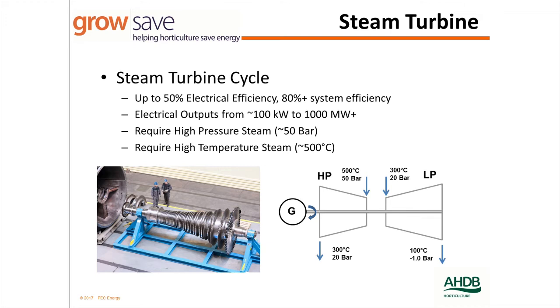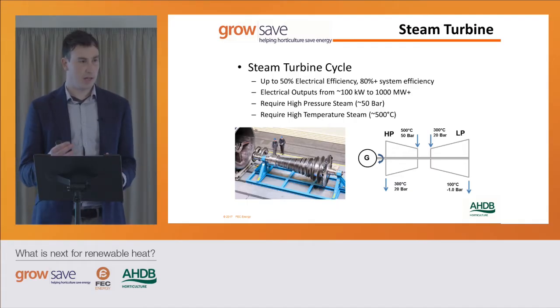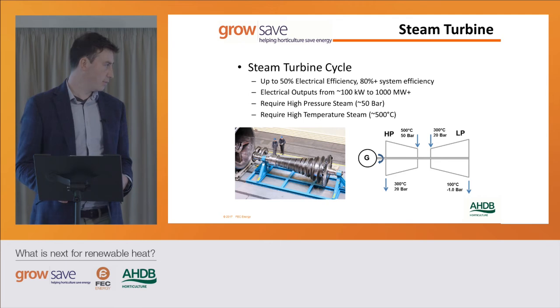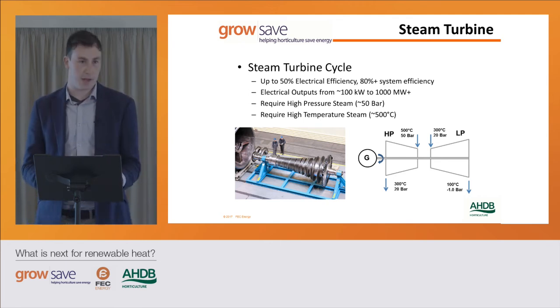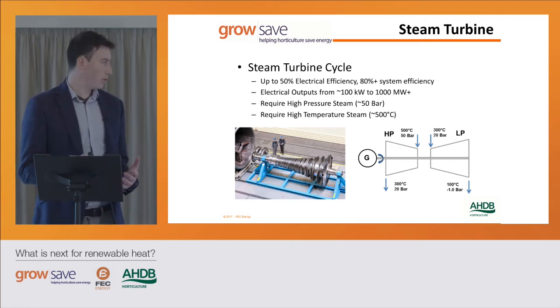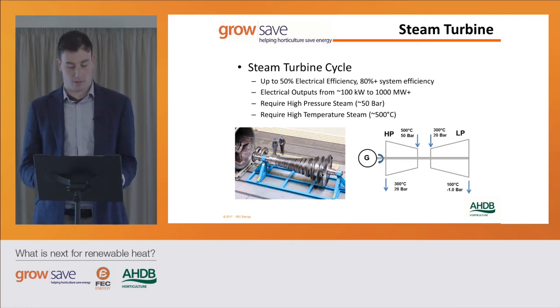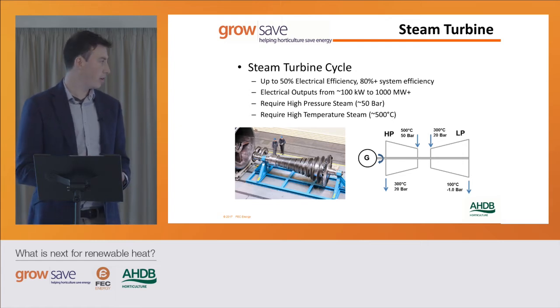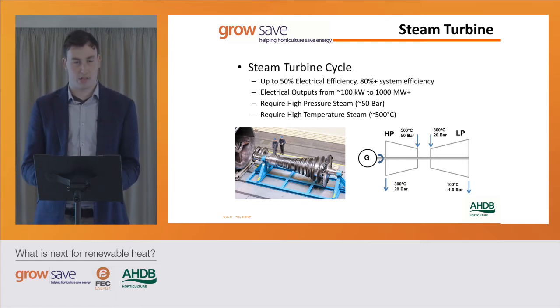The steam from the back end can either be condensed, which helps draw through the steam at a quicker rate—typically what happens in power stations—giving a higher electrical efficiency, up towards about 50%. This does mean the pressure coming out the back end is negative and the temperatures aren't great. You don't necessarily have to condense the steam out the back end though; you can simply use a normal heat exchanger to extract the heat, thereby making it a combined heat and power system.